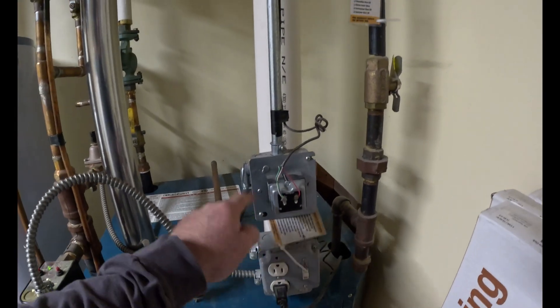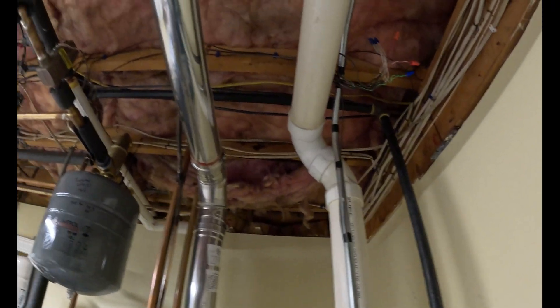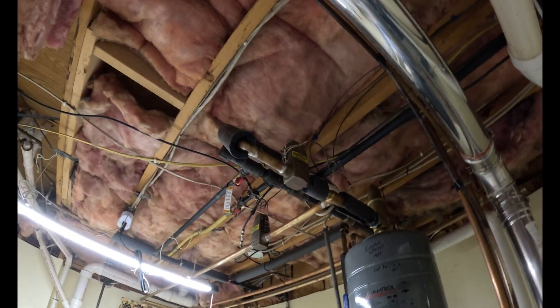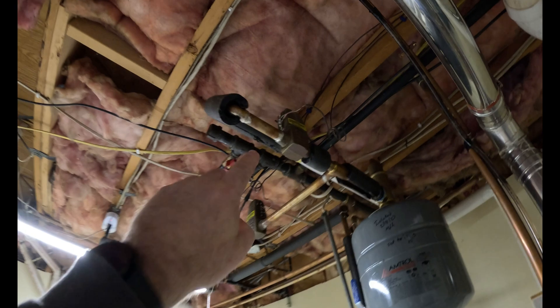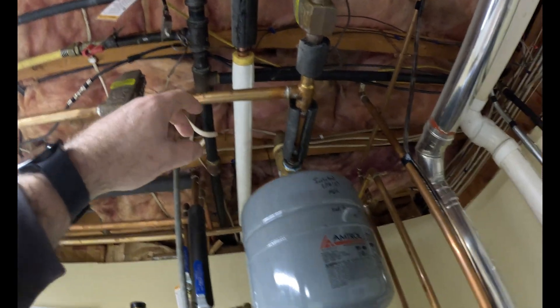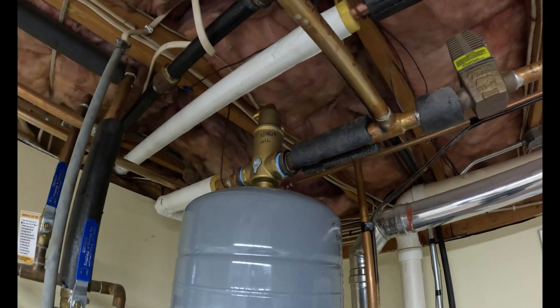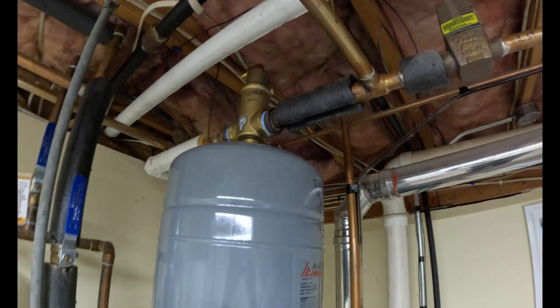Your power here coming in, transformer here to feed your zone valves. So you've got one right here and you've got one right here for the basement zone. Expansion tank off the air elimination device, which is that Spirovent. It's the way to do it.